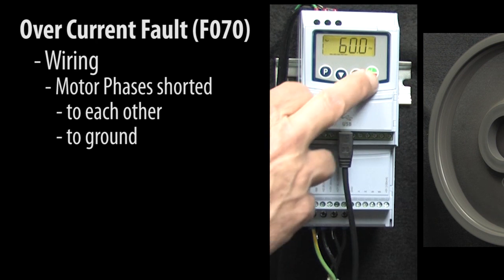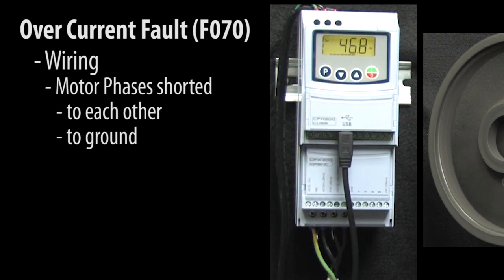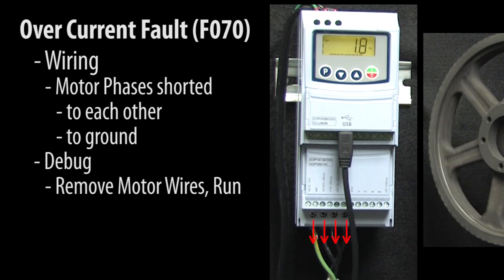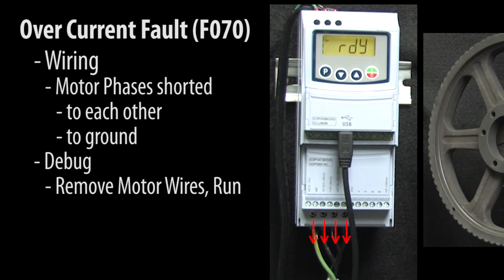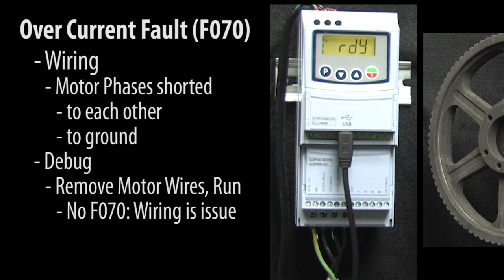So if you get an overcurrent fault, check your motor's wiring. The quickest way to do that is with the drive powered down, remove the motor's wiring from the drive and then hit run. If the drive runs without a fault, then there's definitely something wrong with the wiring to the motor or the motor has an internal short.